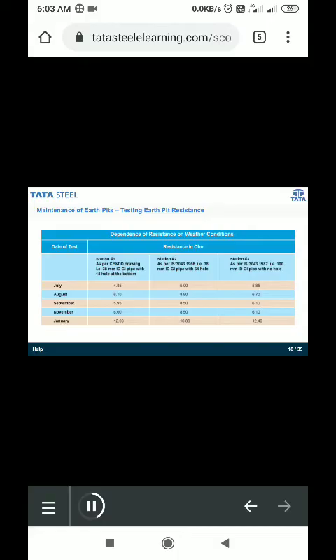The table here conveys how the resistance of the earthing pit varies depending upon the seasonal condition. For example, if you take a look, the value of each month differs. While there is a lower value in July, January has a higher value. Therefore, you can see that the resistance values vary with the season. Also, if you look at the last row, the values have been consistently high in the month of January across all the 3 stations. Therefore, maintenance of each earth pit should be done when the resistance values are high. Further, this maintenance should be done during the dry seasons only, that is between January to March.